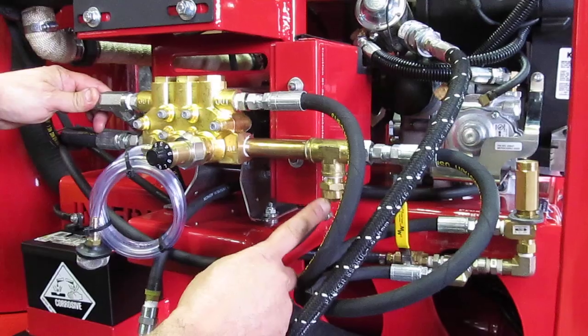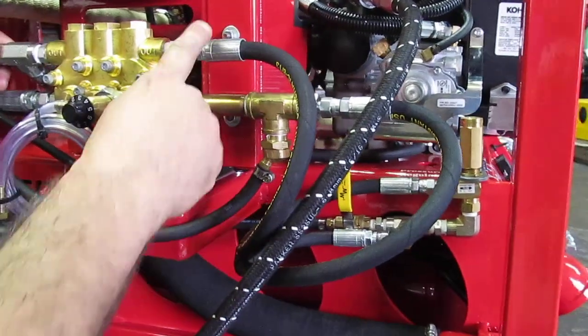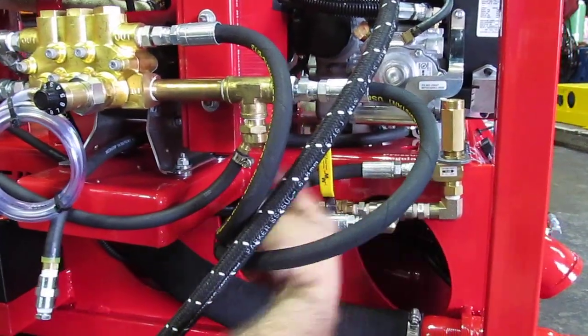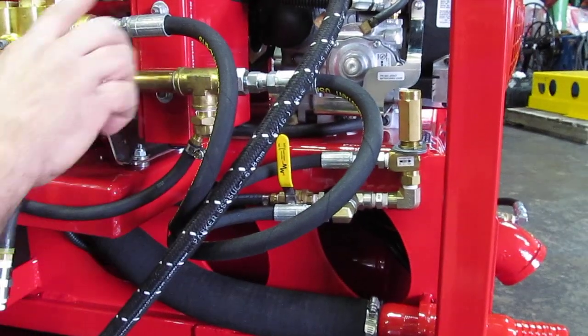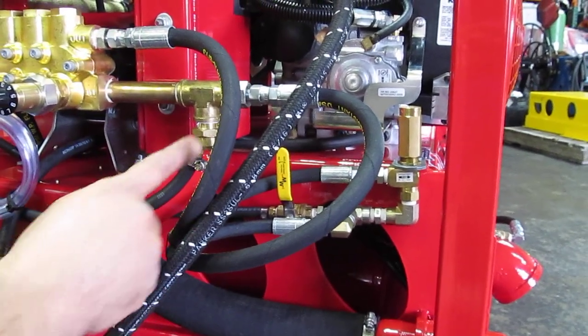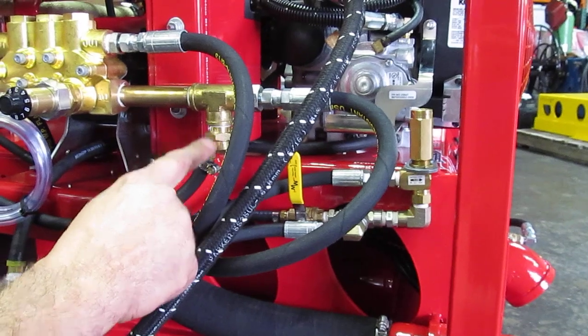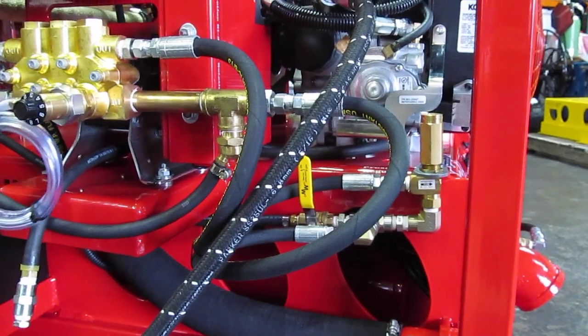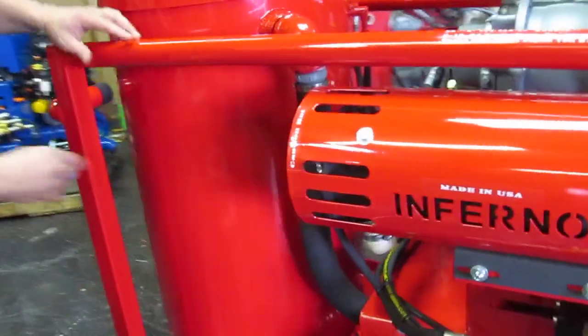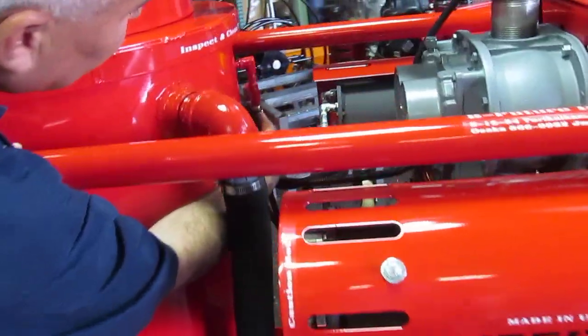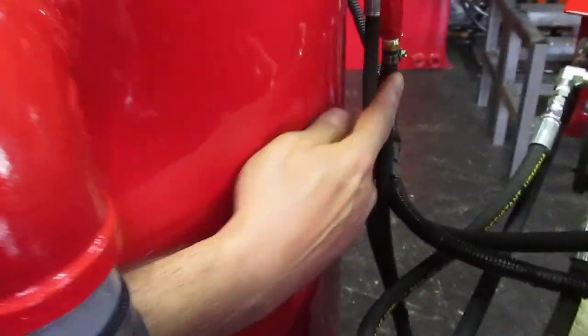Your thermal relief valve is right to the right side, which, as the water loops around into the regulator and comes back, if the temperature reaches over 140 degrees, this popper valve will open and slowly allow water to start traveling. If we take the camera all the way up, you come in here and it will spit it into the tank.